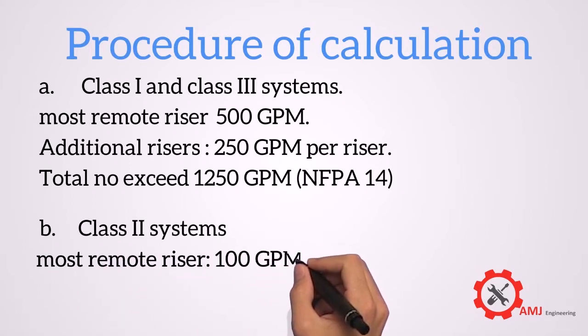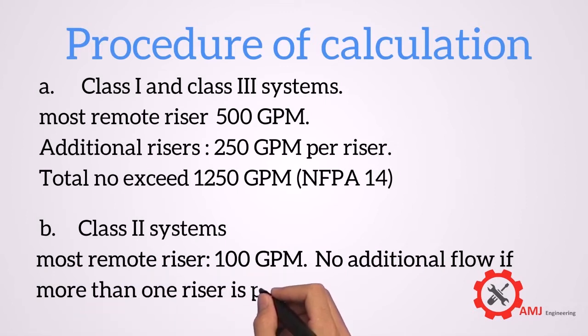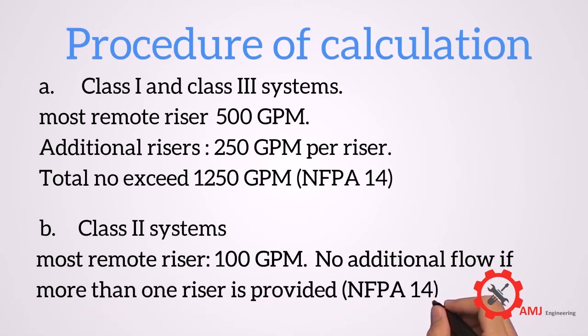For class 2 systems, the minimum flow rate for hydraulically most remote riser shall be 100 GPM. Additional flow needs not to be added when more than one riser is provided.